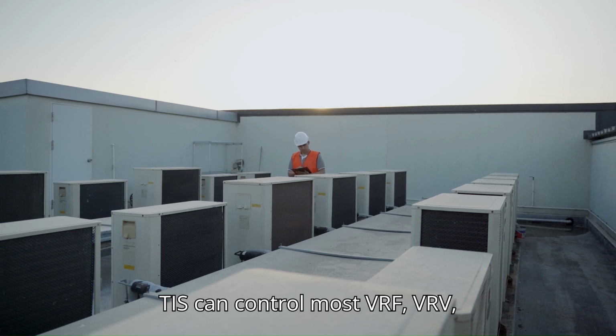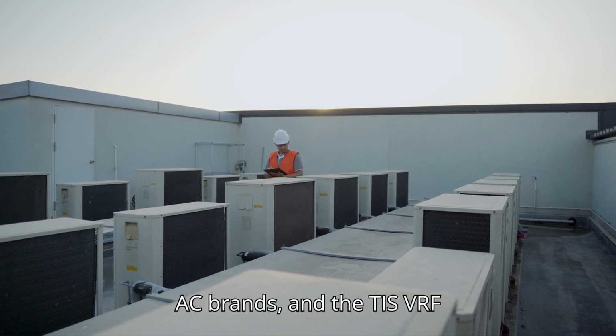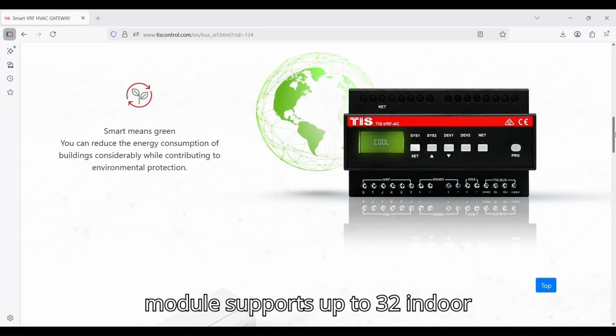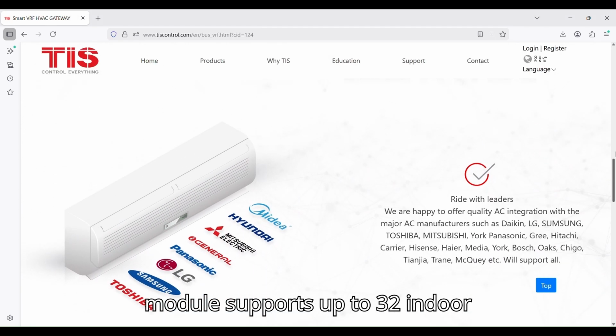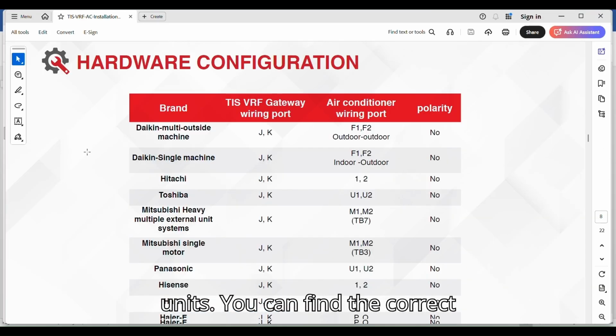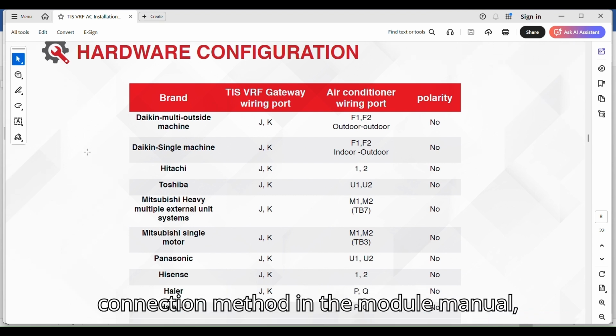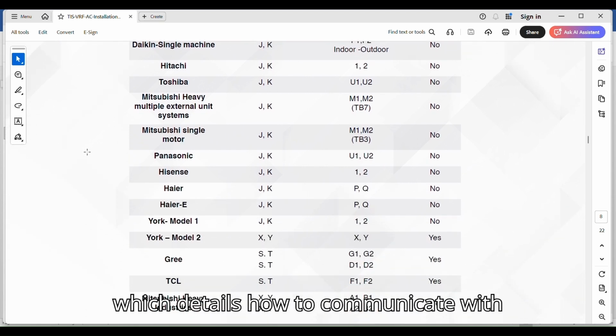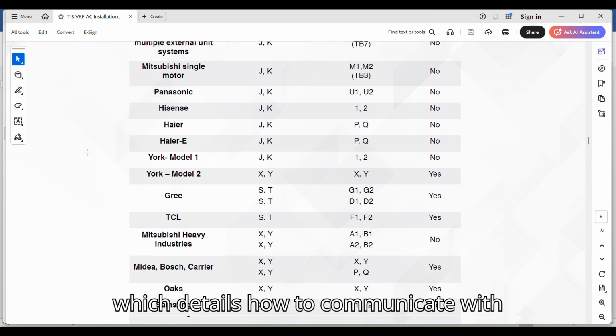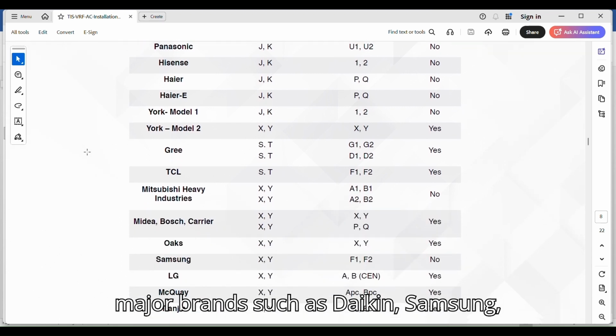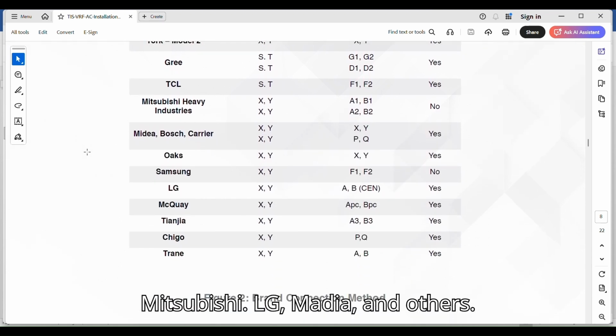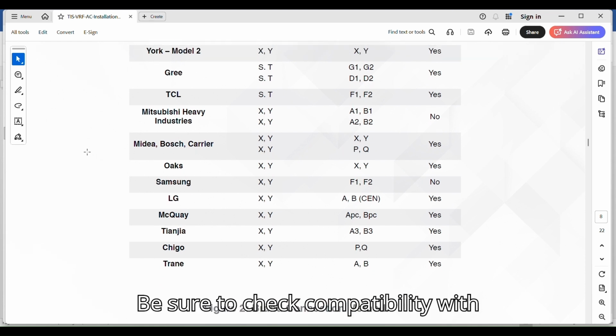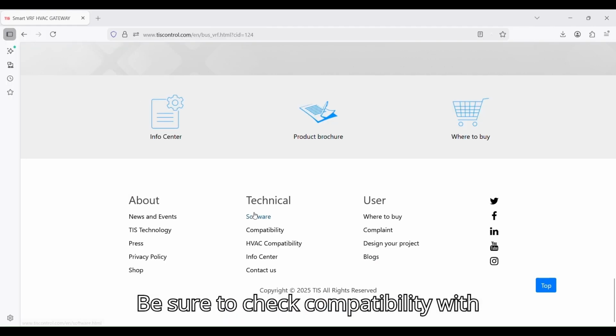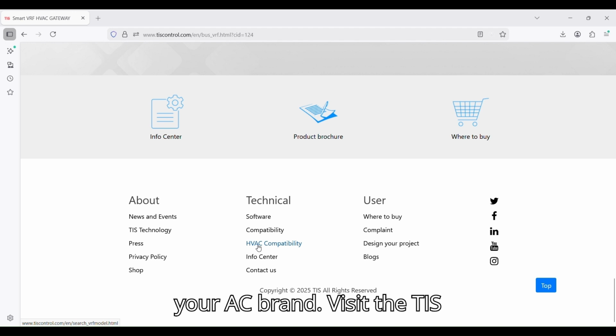TIS can control most VRF VRV AC brands, and the TIS VRF module supports up to 32 indoor units. You can find the correct connection method in the module manual, which details how to communicate with major brands such as Daikin, Samsung, Mitsubishi, LG, Midea, and others. Be sure to check compatibility with your AC brand.